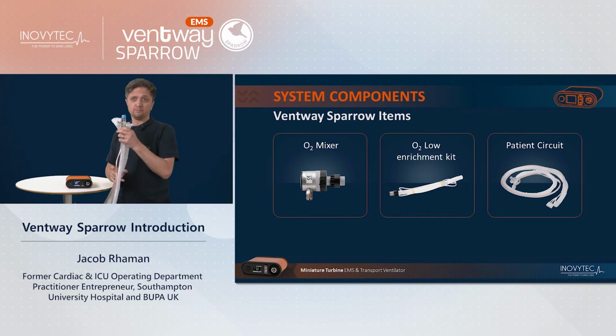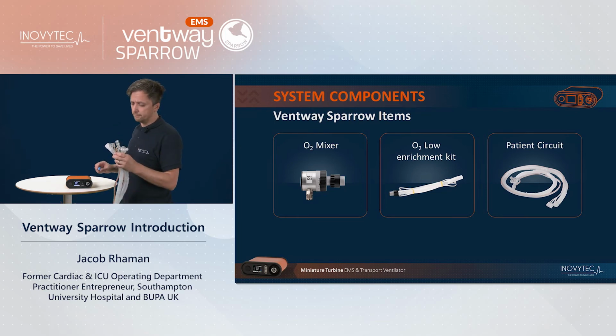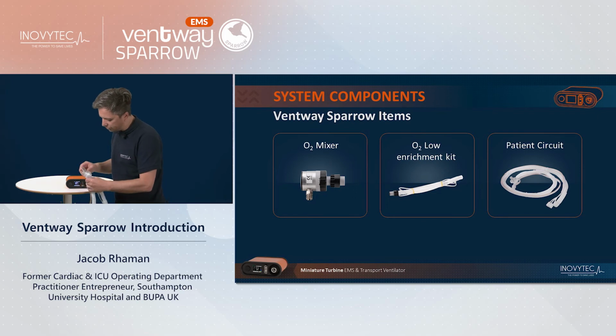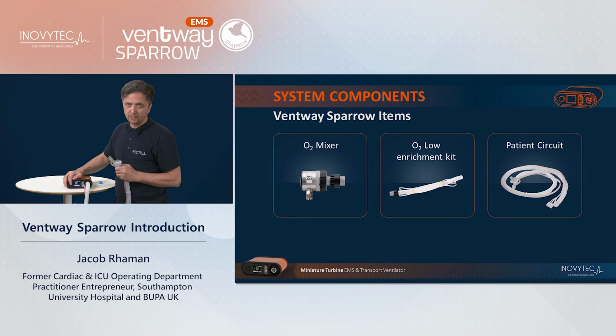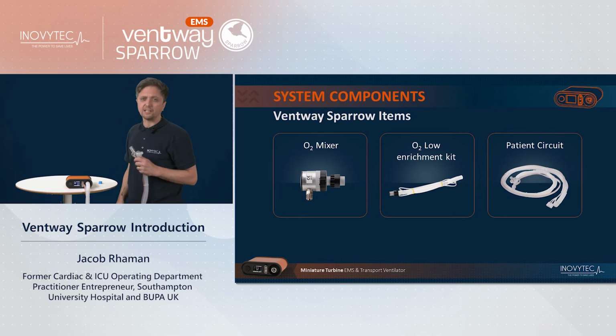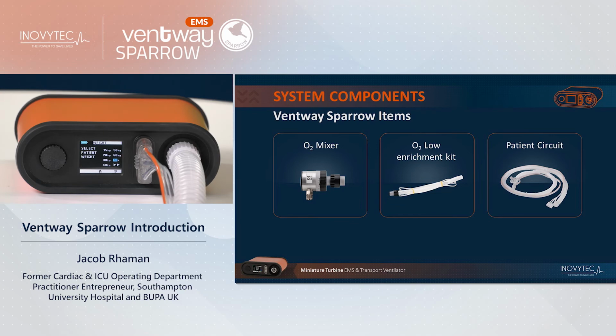To test the Ventway Sparrow ventilator, we have to take a single-use patient circuit. Let's remove the blue cap, attach the patient circuit as shown before with the orange line facing upwards, and simply press the jog wheel. It should take around about 12 seconds. The ventilator is now ready for use. Let's take a closer look at the display.